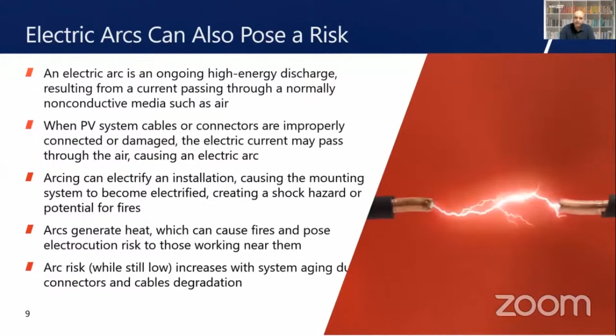Now, a number of solutions have been tried to address some of these risks. The first one that most people will be familiar with is the installation of automatic DC breakers at the inverter. Whilst these effectively terminate DC voltage at the inverter, they're not disconnecting at the module level. So effectively what this does is add cost, but it does nothing to mitigate the risk associated with high DC voltage on the DC cables coming from the modules.